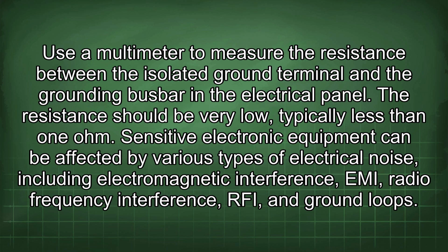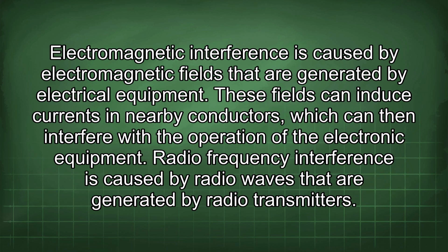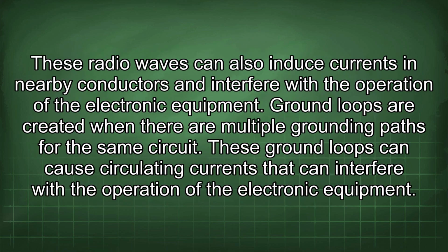Sensitive electronic equipment can be affected by various types of electrical noise, including electromagnetic interference, EMI, radio frequency interference, RFI, and ground loops. Electromagnetic interference is caused by electromagnetic fields that are generated by electrical equipment. These fields can induce currents in nearby conductors, which can then interfere with the operation of the electronic equipment. Radio frequency interference is caused by radio waves that are generated by radio transmitters. These radio waves can also induce currents in nearby conductors and interfere with the operation of the electronic equipment. Ground loops are created when there are multiple grounding paths for the same circuit. These ground loops can cause circulating currents that can interfere with the operation of the electronic equipment.